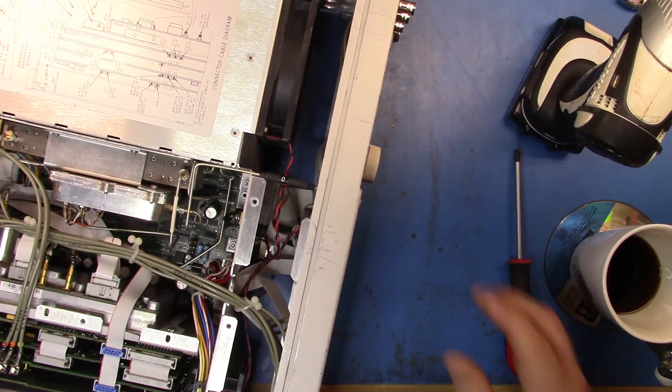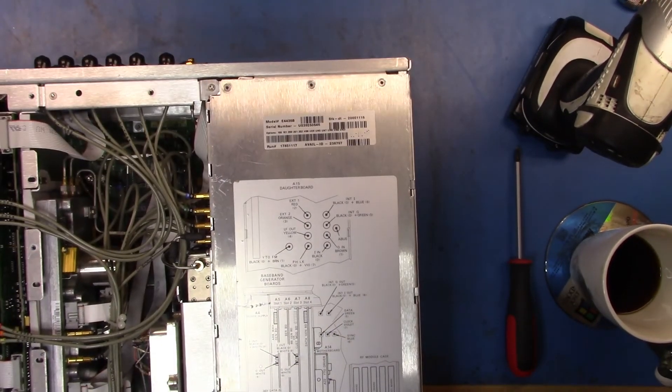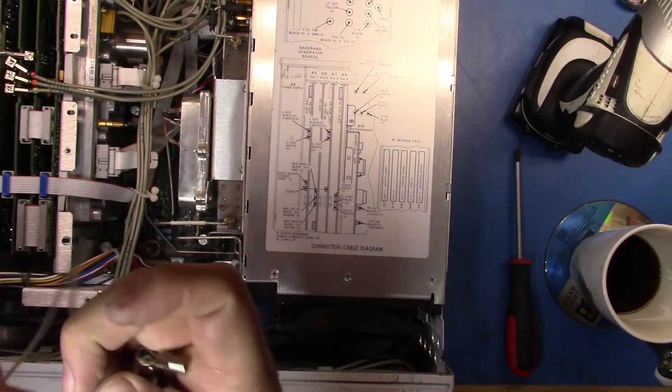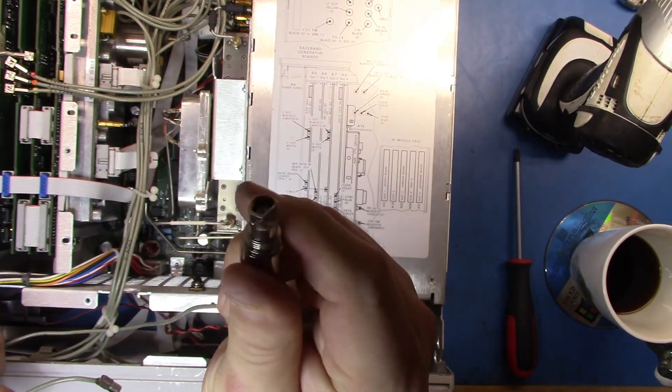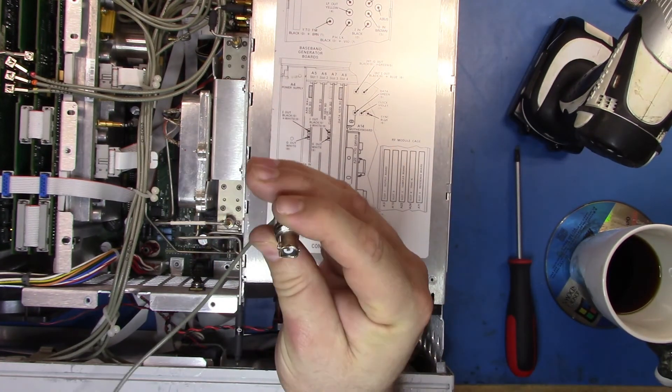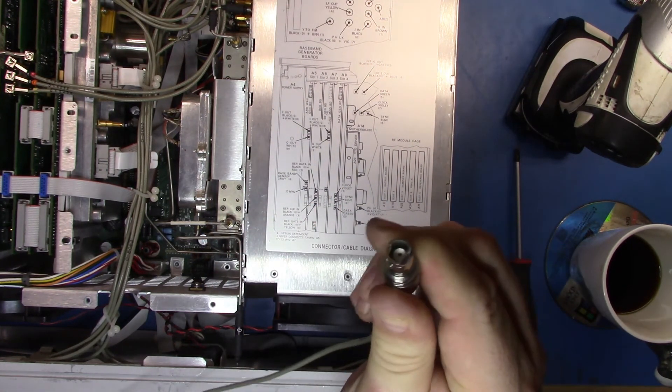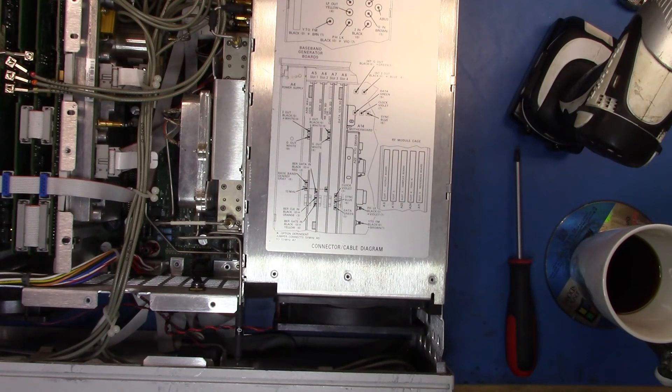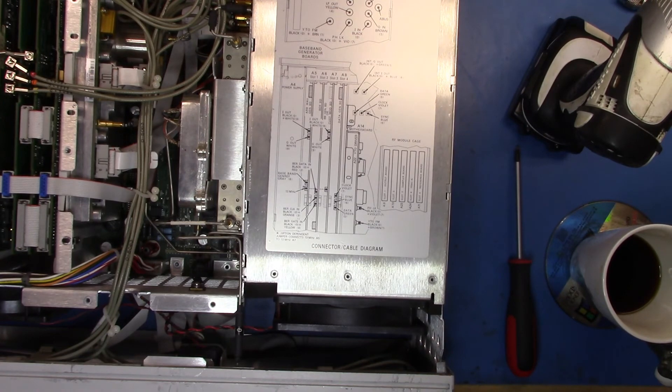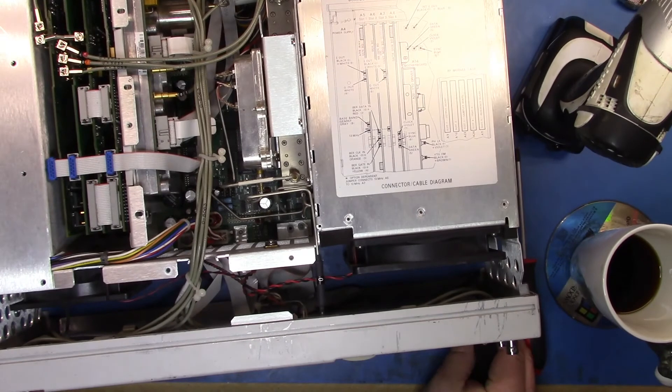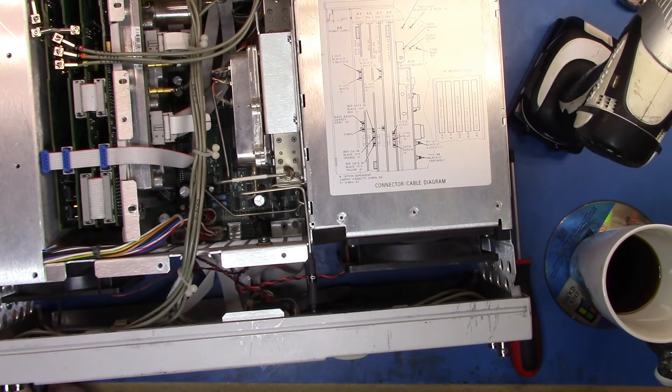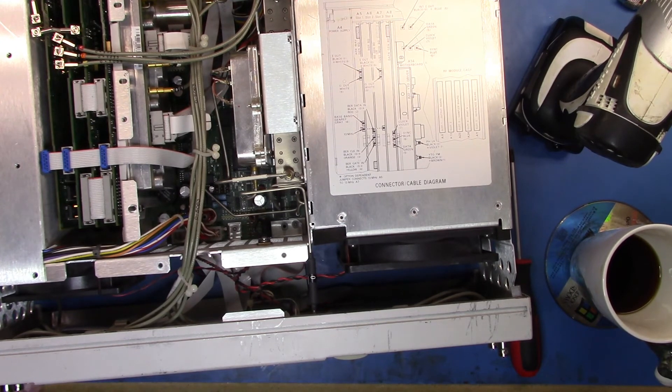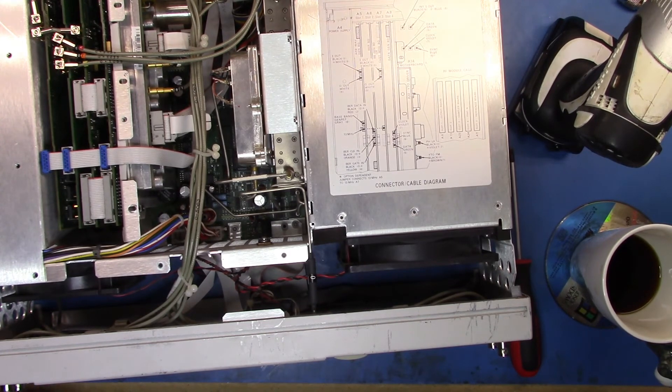There we go. Now I can put the washer and the nut back on, and we have our item in here. Let me just tighten that down. Nice. There we go, and you can see the damage they did to the connector where it's just blown through, driven through the side of another case there. Let me grab a BNC cable and just test all those front connectors. They're all fine. The new one, yep, data clock, yep, the inner connector looks fine.